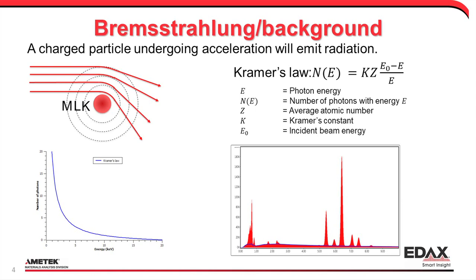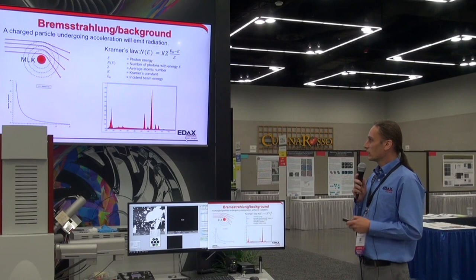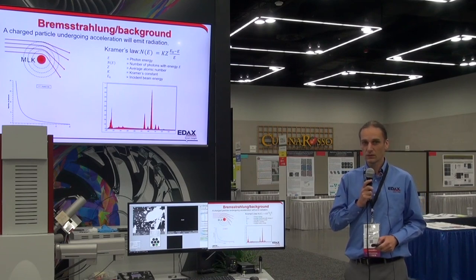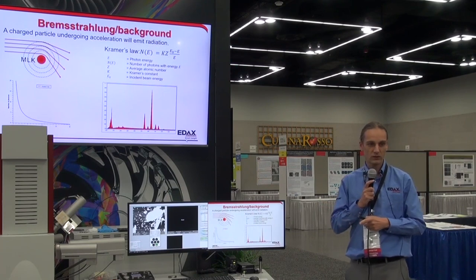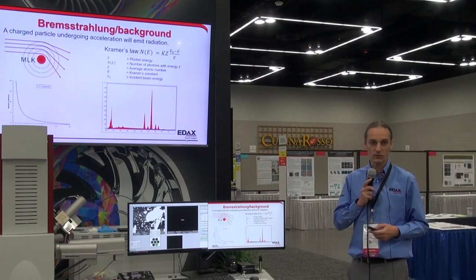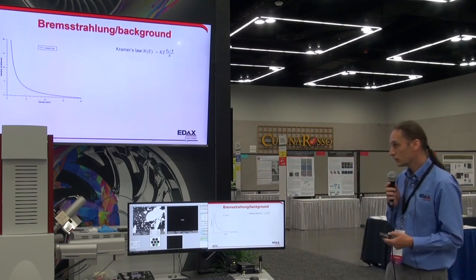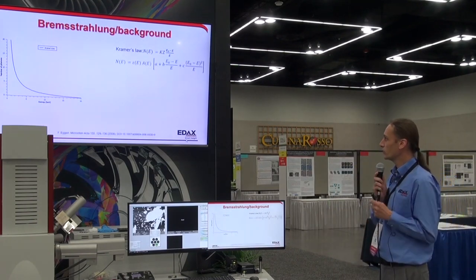If we plot that out, we have the curve from Kramers' law and compare it to what we see in an EDS spectrum — they don't really look anything alike. In the EDS spectrum it drops off towards the low energy range, whereas Kramers' law says it should go up, basically continuing towards infinity. The difference is Kramers' law describes what's emitted. What we have in the spectrum is what's detected — the emitted x-rays have to make it out of the sample and through the detector before we can count them. So our modeling is not based on Kramers' law directly; we use a modified model.